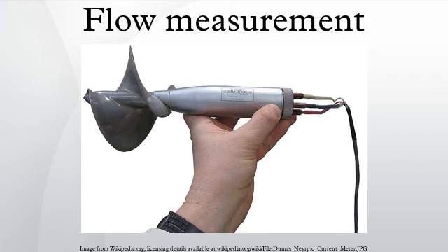Level-to-flow devices are commonly used to measure the flow of surface waters, industrial discharges, and sewage. Of these, weirs are used on flow streams with low solids, while flumes are used on flows containing low or high solids contents. Area/velocity: the cross-sectional area of the flow is calculated from a depth measurement and the average velocity of the flow is measured directly. Velocity times the cross-sectional area yields a flow rate which can be integrated into volumetric flow.